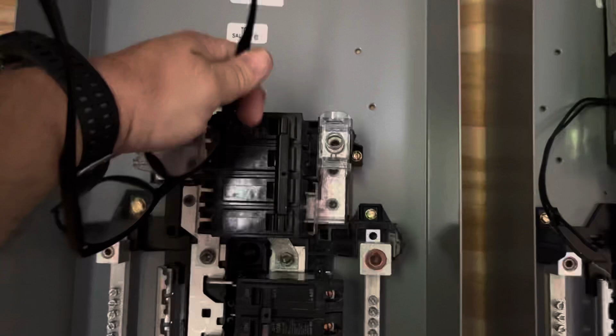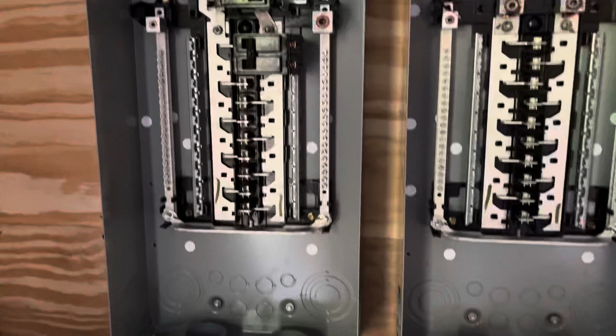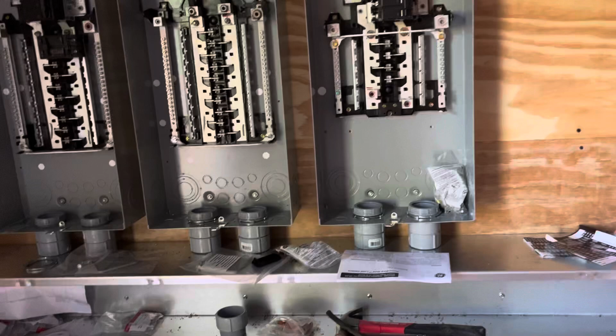The power coming in from the breaker panel is going to come up and feed this panel, and this will be the inverter feeder panel. So it'll be 5 breakers here feeding the 5 inverters. And then the output from this panel, which is going to actually be the system output panel, I will be feeding off these lugs going to the transfer switch. Then of course this one here is going to be my inverter output panel, and it'll run through the transformer. Transformer will come here, and this will be my solar power output panel, where I'll get my neutral. I'll derive my neutral through the transformer. So anyway, that's the plan.